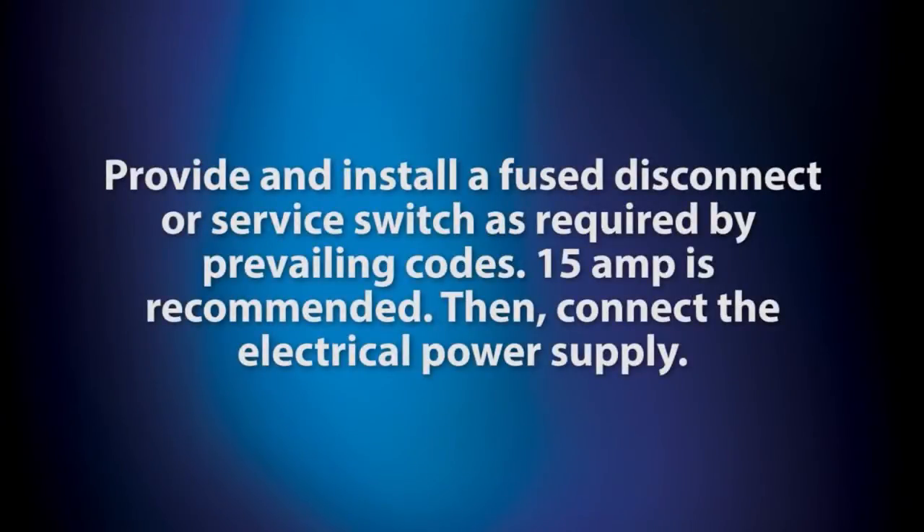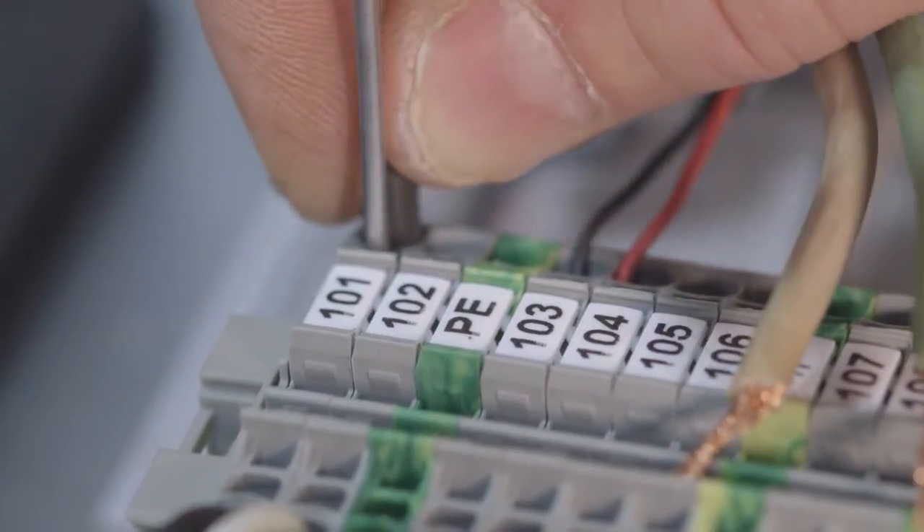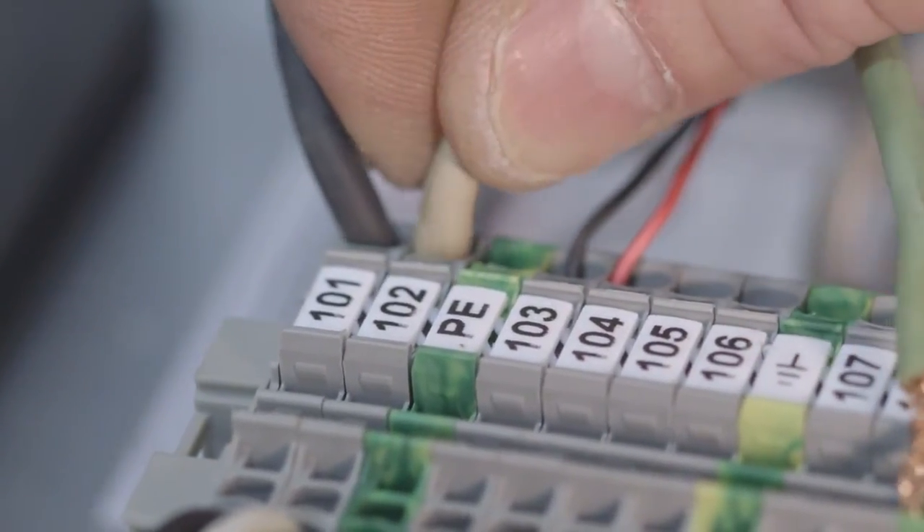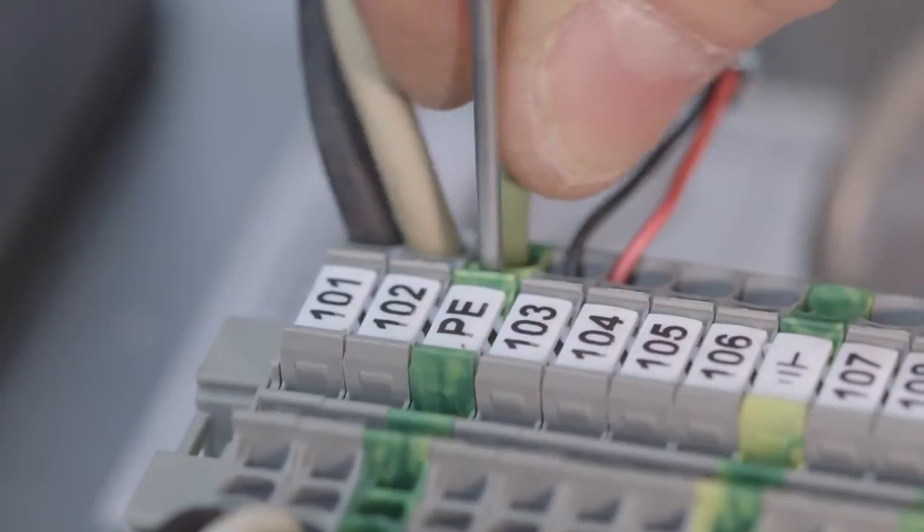Provide and install a fused disconnect or service switch as required by prevailing codes. 15A is recommended. Then connect the electrical power supply. Connect the line cable here. Connect the neutral cable here. Finally, connect the ground cable as shown here.